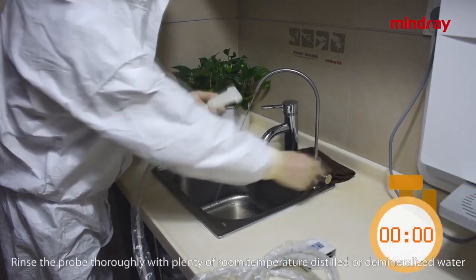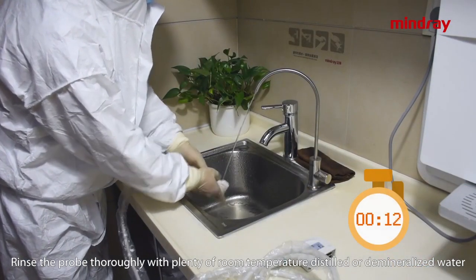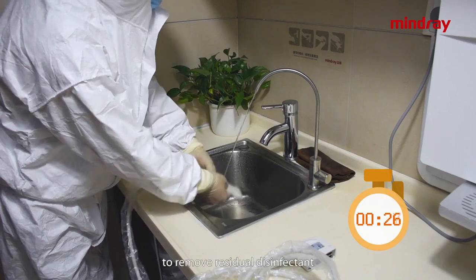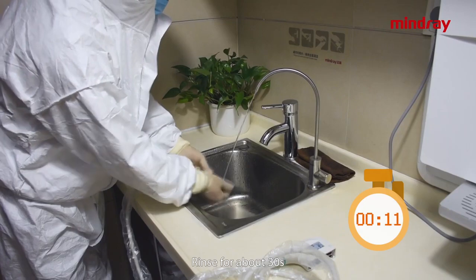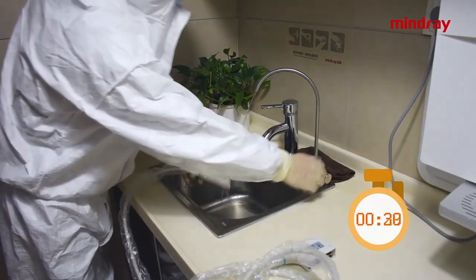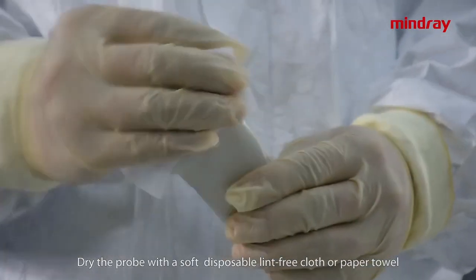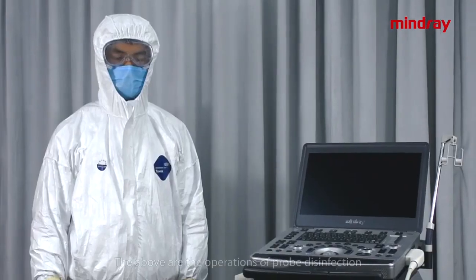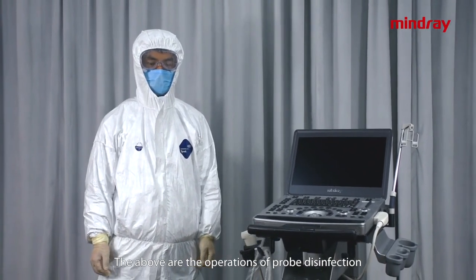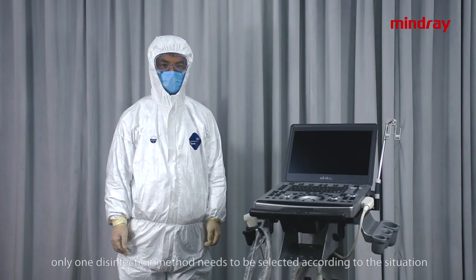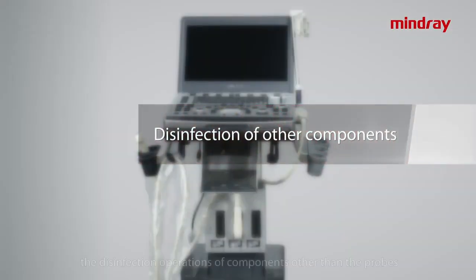Rinse the probe thoroughly with plenty of room temperature distilled or demineralized water to remove residual disinfectant. Rinse for about 30 seconds. Repeat twice. Dry the probe with a soft, disposable lint-free cloth or paper towel. Caution: never dry the probe by heating. The above are the operations of probe disinfection. In actual application, only one disinfection method needs to be selected according to the situation. The following will demonstrate the disinfection operations of components other than the probes.